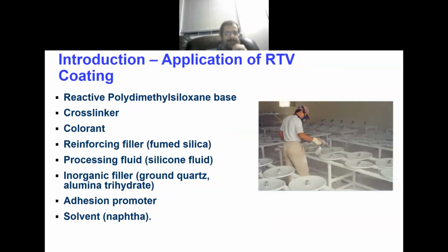Now let's come to Qatar. How does Kahramaa use this technology? They use it in a different way—they don't go to the site and spray the insulators, but use what we call pre-coated insulators, as you can see here. Basically, they use glass insulators, the ones Dr. Muhammad showed at the beginning, and these insulators are pre-coated and then used in the field. There is no coating done in the field, because coating in the field is very hard to control. So this is the technology used now.